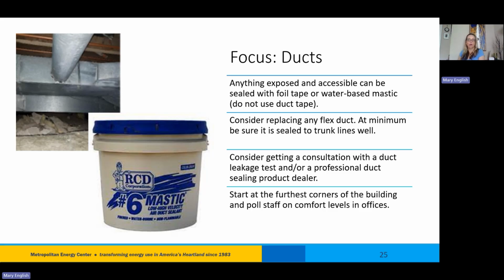Next focus is the ductwork. I can't stress enough how important it is for our delivery system to not leak. Conditioned air should be considered a fluid, like water - you don't want your water pipes to leak, right, that leads to damage. It's more well known what kind of damage you get from a leaky water pipe than a leaky duct. But if ducts are very leaky, that means the air to rooms farthest from the air handler, from the heating and cooling system, may be consistently cold in the winter and hot in the summer.